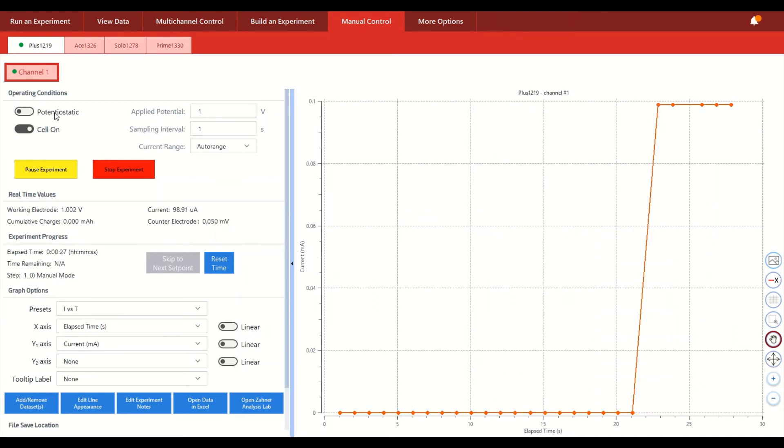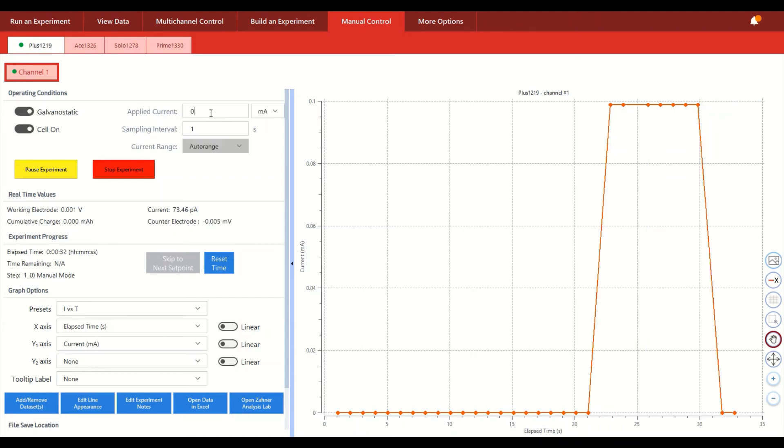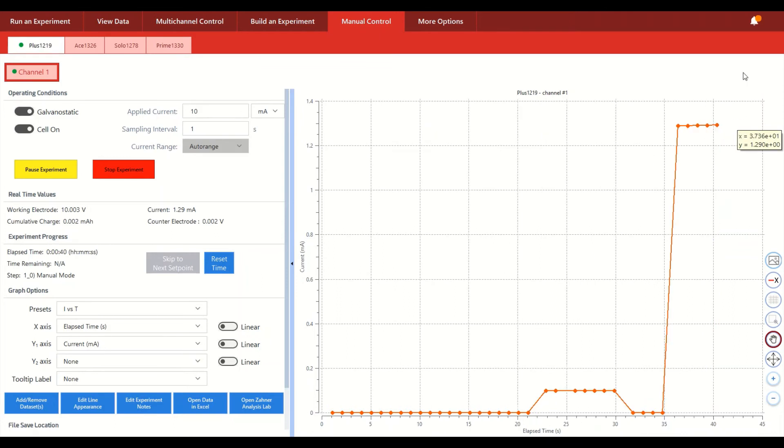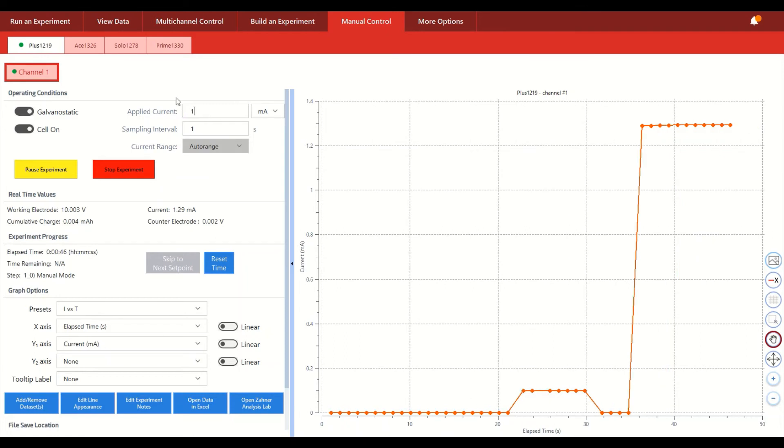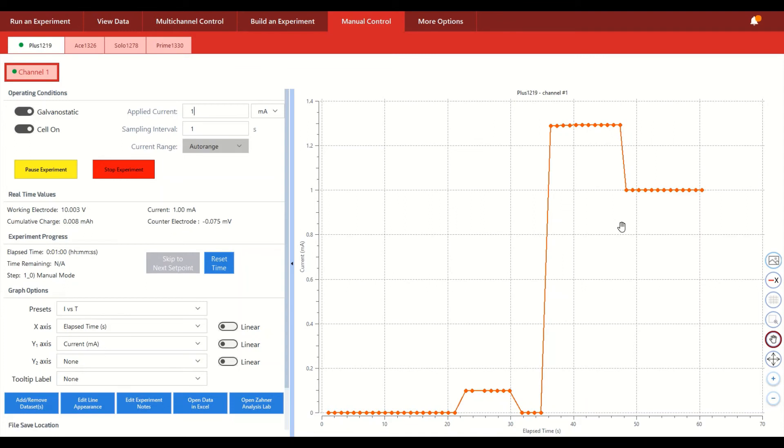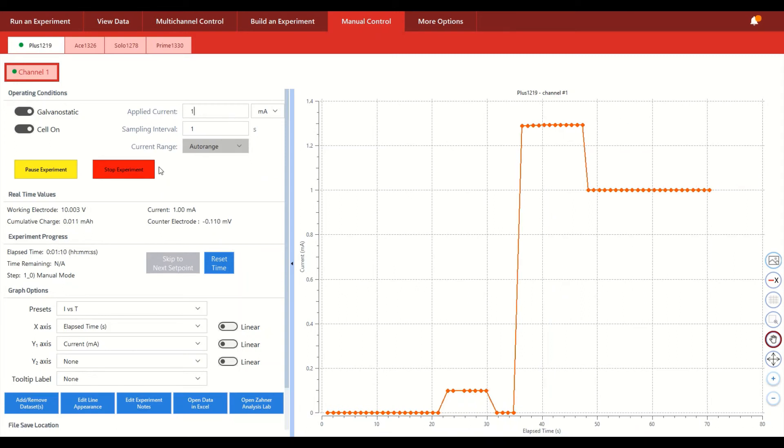And you can also toggle between being in potentiostatic mode or in galvanostat mode. So here we go, we can apply 10 milliamps, which I guess is outside the voltage limit for this Randles cell that I have connected, so we can go a bit lower than that. And with this mode, with the example like I just showed here, where I don't necessarily know the limits of the sample that I'm testing in terms of the specifications of the instrument, you can use this as a time saving measure to easily figure out what sort of voltage or current set points you should plan to configure into say a CV or perhaps doing some impedance measurements.